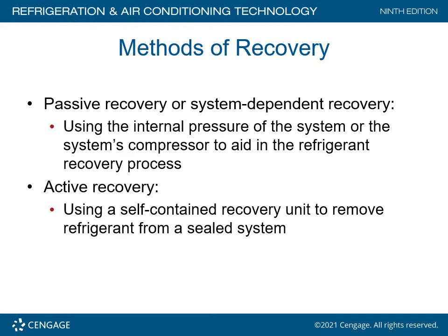Methods of recovery. Passive recovery, or system-dependent recovery. This is the term that is used when you're recovering and it utilizes the internal pressure of the system or the system's compressor to aid in the refrigerant recovery process. So as an example, you could utilize a working compressor to push the refrigerant out of a system into a bottle, or in the case of a small appliance, a Whirlpool bag.